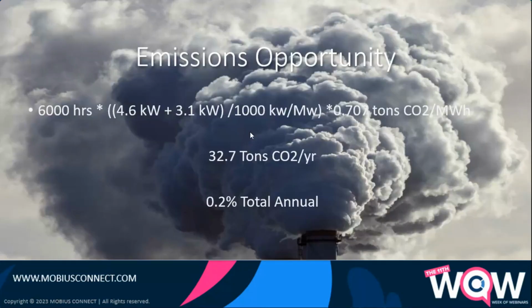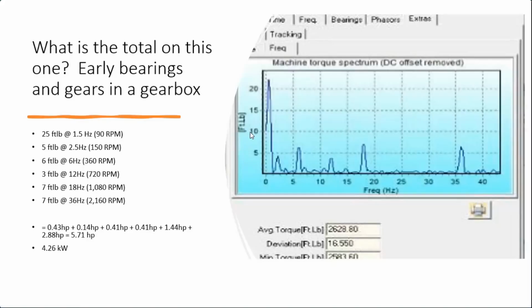So just doing that one machine, a 150 horsepower machine, belted fan, we're talking about doing proper tensioning and alignment of 32.7 tons of CO2. Good news behind that, by the way, the belt wasn't worn. It was just misaligned and not tensioned properly. So they were able to recover it. The actual application dropped it. Now, you won't get all 32.7 tons because there'll still be some friction losses in there, maybe a little bit of slip. So I figured that dropped down to about 28 tons reduced.